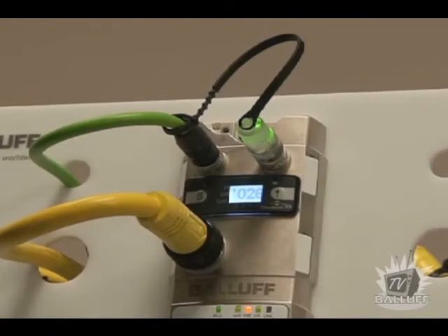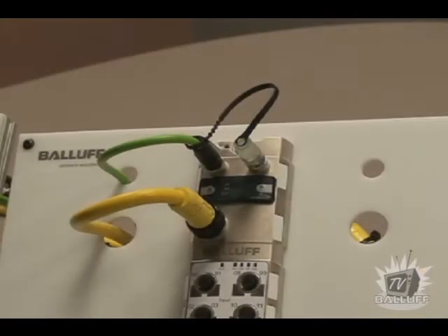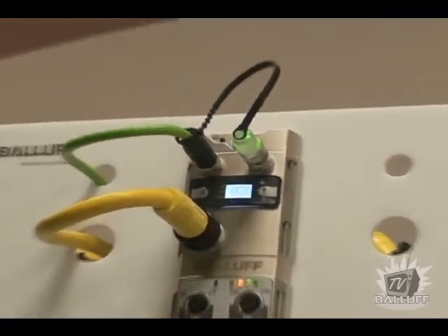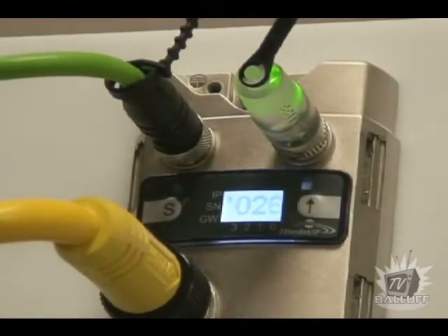In a current installation where an issue may occur, the block can be quickly hot-swapped with another block. When removed, the IP address remains with the location and the network configuration stored in it. Once the cables and IPAP are reconnected and powered on, the block is automatically configured with the addresses.